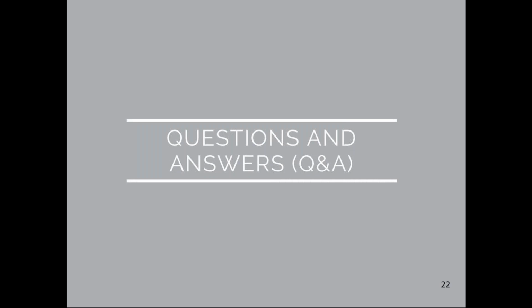Looking at more questions: can you mix AGM or sealed lead acid batteries with lithium-ion? You could - I've seen people try to build hybrid energy systems with cheaper lead-acid batteries for capacity and lithium-ion or ultracapacitors for high power and long life, and it doesn't usually end up working out. It looks good on paper, but by the time you look at the electronics or DC-DC converters needed between the two energy systems, I wouldn't recommend it.